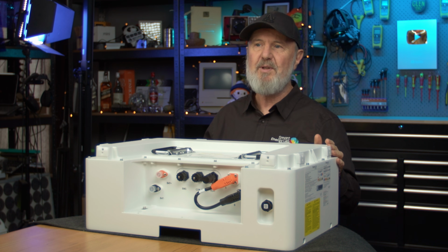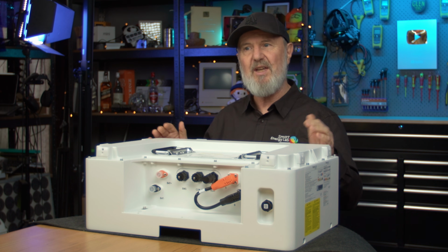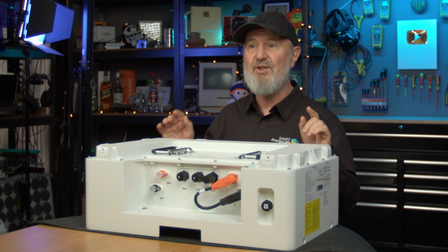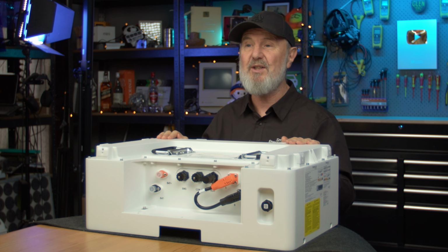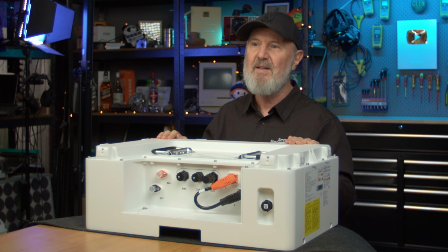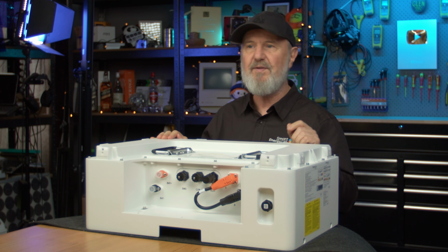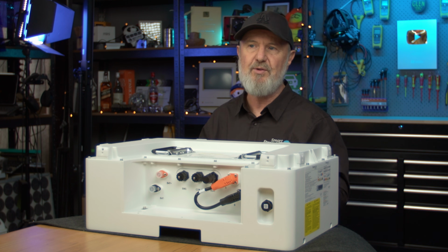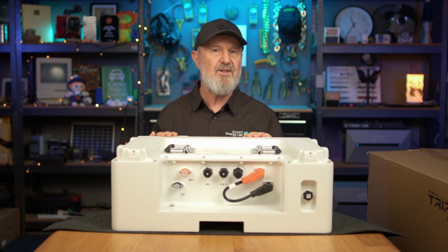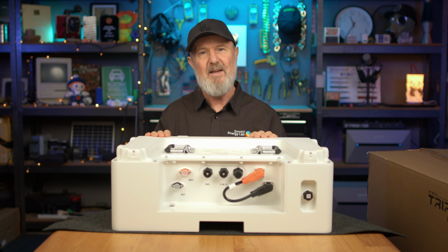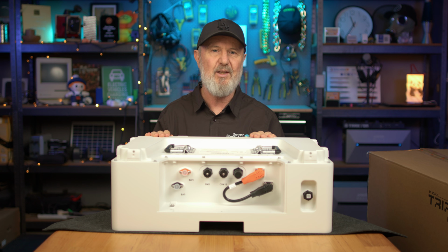Now, when it comes to performance, as I said, a maximum per stack of 51.2 kilowatt hours usable. That's the number that matters when it comes to the Cheaper Home Battery program, and a nominal voltage of 51.2 volts for each battery module. When they're connected up in series, you've got a 70 amp charge-discharge current capability, which means with the full stack, peak power of greater than 20 kilowatts.